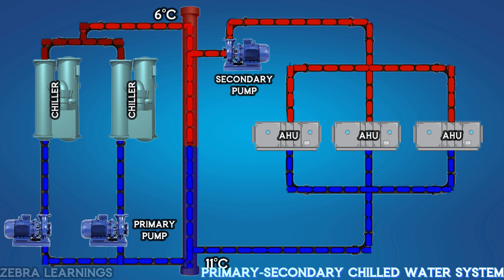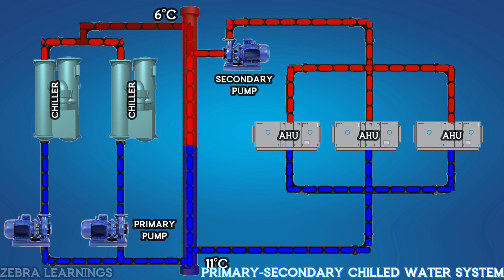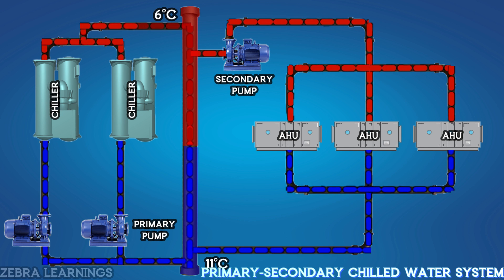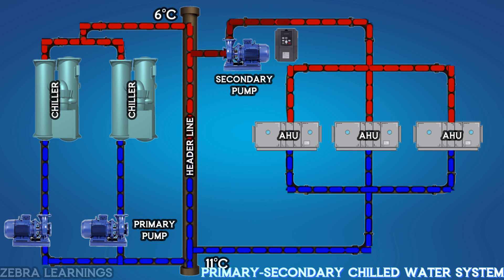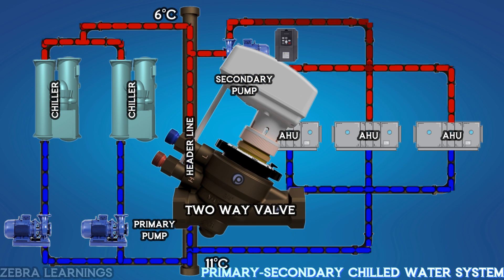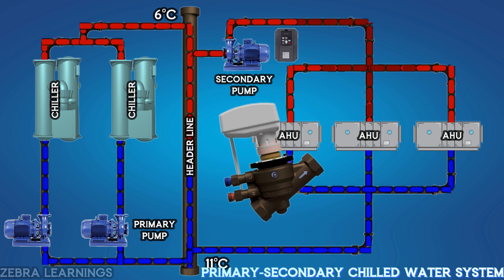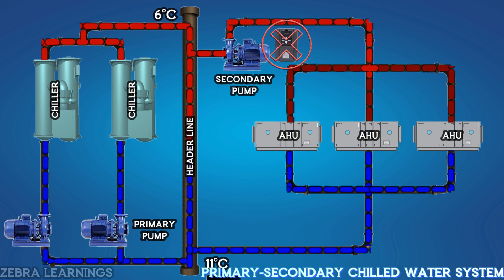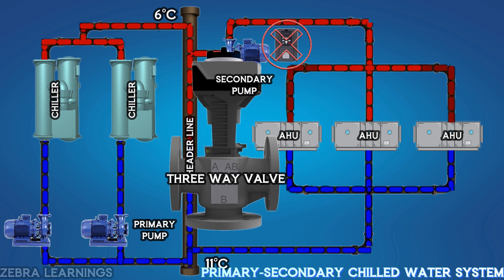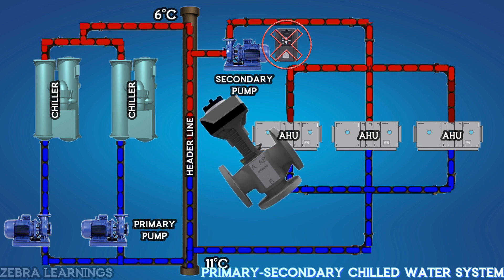There are two separate chambers in the header line, so the water from the chiller and the water from the AHU do not mix. If a VFD is used in the secondary pump, a two-way valve is used in the AHU. If a VFD is not used, a three-way valve is used in the AHU.